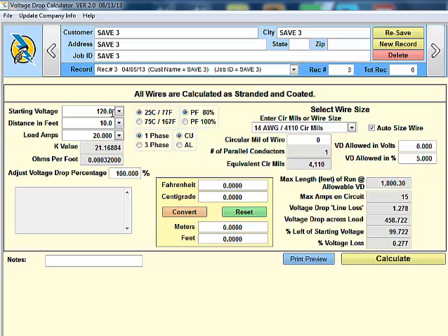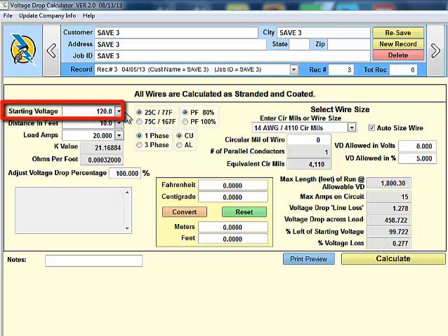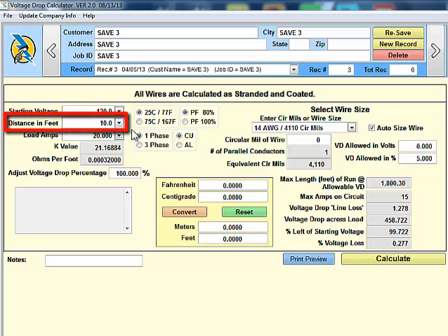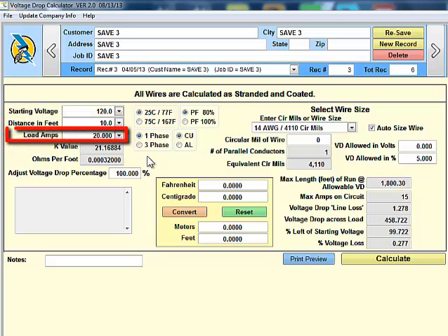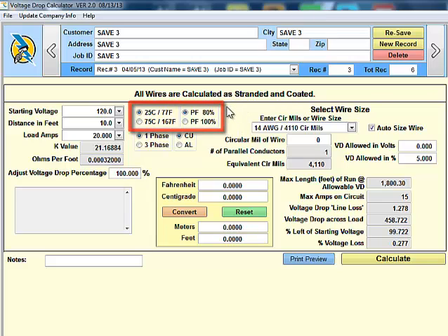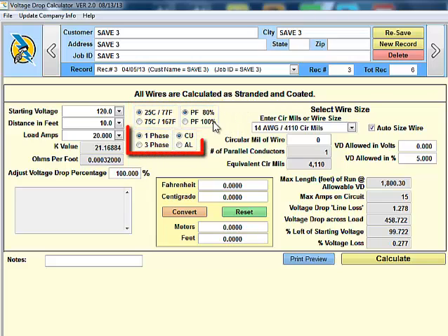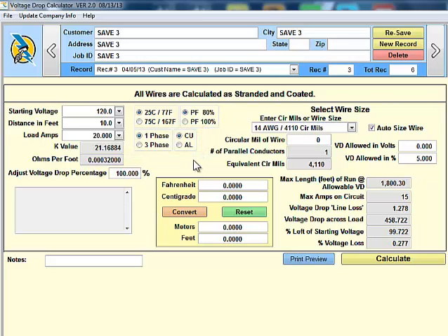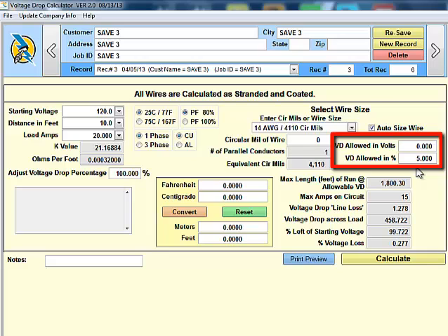At this point we can see what we've already saved. Had a starting voltage of 120 volts, a starting distance of 10, load amps of 20 amps, and we're at 25°C, 77°F, and an 80% power factor, one phase copper, and we're trying to keep the voltage drop within 5%. We could also change it to a voltage up here.